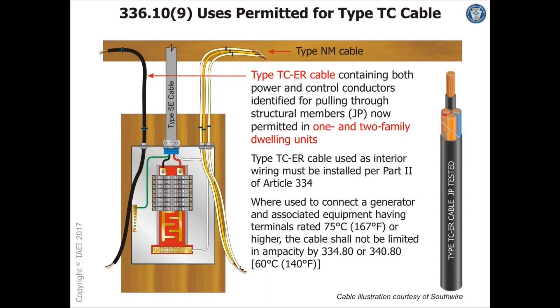Type TC-ER means the cable is suitable for exposed run — ER stands for exposed run. Type TC-ER could also have the suffix JP, which stands for joist pull.